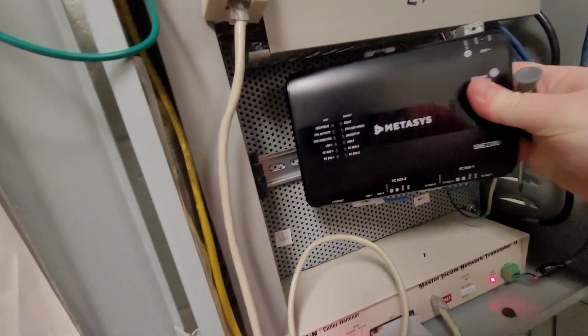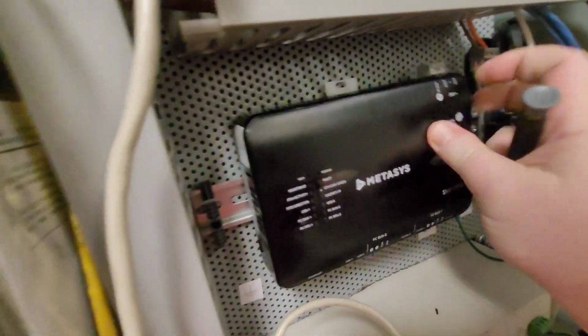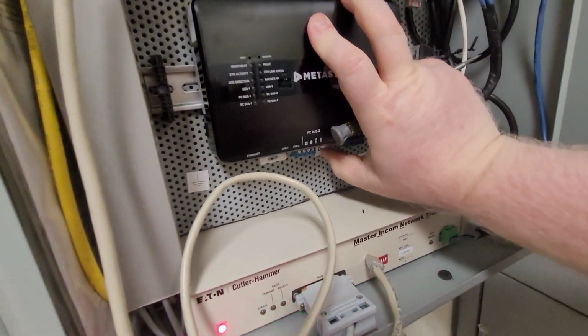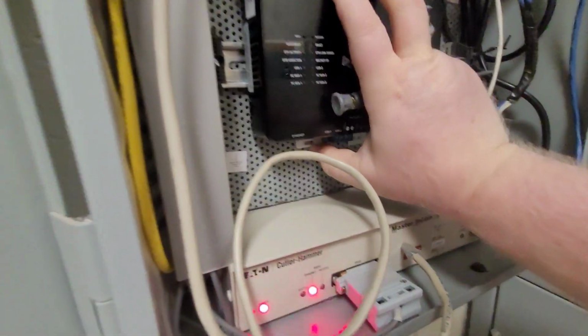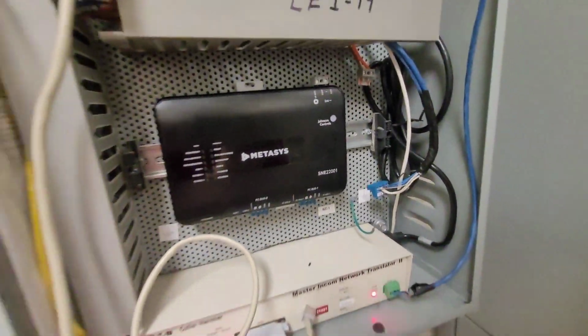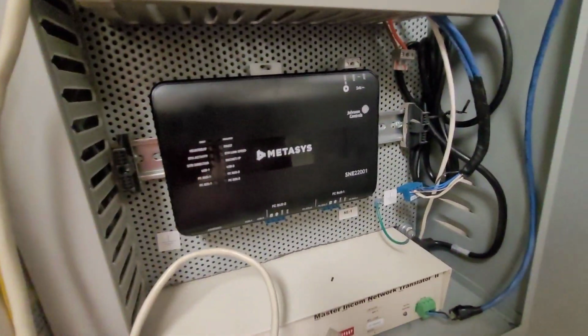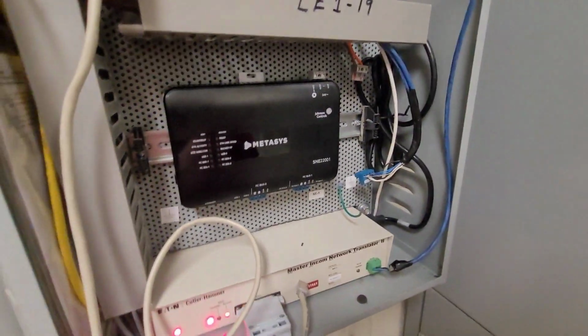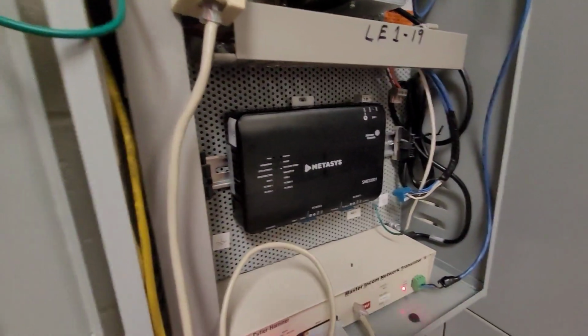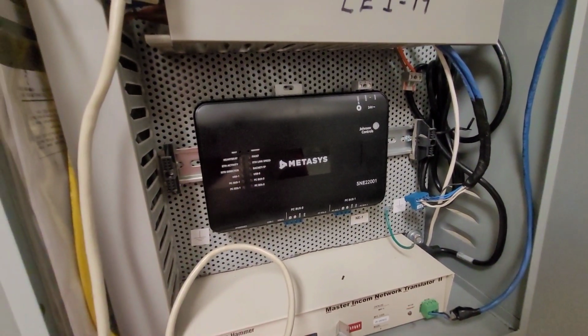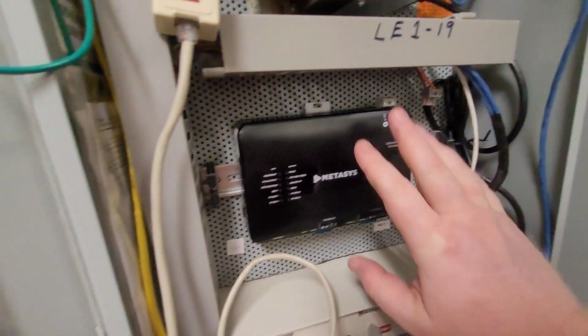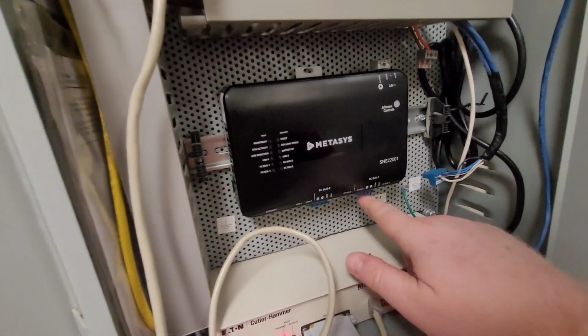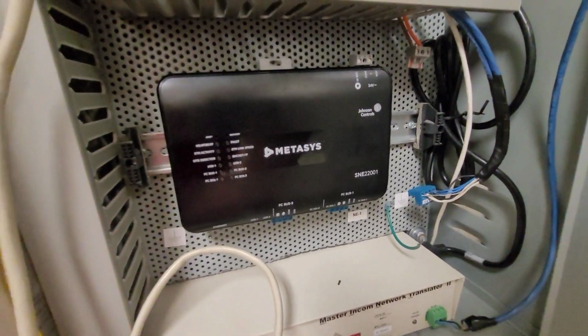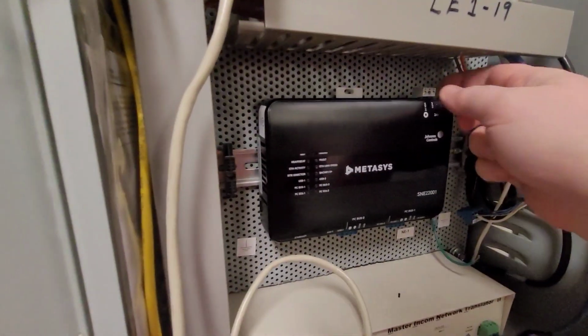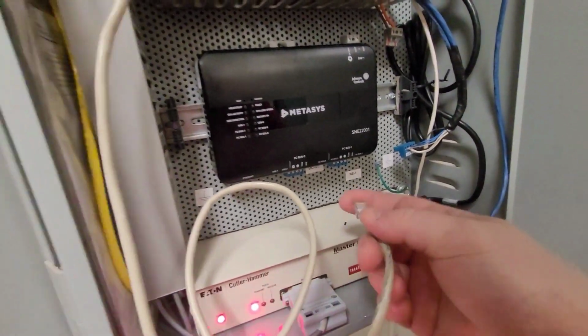actually going to be adding some BACnet devices, because currently this trunk is mostly N2, but with technology changes, with some of the stuff that we've got going on, we are needing a BACnet trunk for this building. We're going to be pulling in some metering and things like that. We're having to upgrade a flow meter, so we've gone ahead and gotten a new flow meter that talks BACnet, and having the availability of the trunk is going to give us a lot of options to be able to turn this system up a notch.